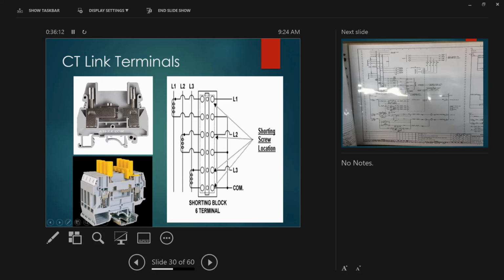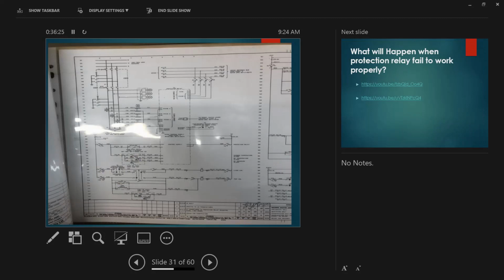That is the representation of the single line. This is from the CT, and this side will go to the relay. Mostly you can see this on the drawing like this. This is your protection relay, and this is your voltage. Of course, you have the feed from the VT going here, and the CT going here. If you test the relay, make sure that the VT is isolated. Because if that one is closed and the incomer is energized, you still have VT voltage here, and if you connect your test equipment over there, it will bugger the test equipment. Another 30 grand, according to Steve. So we have to be careful, especially when looking at the schematic, make sure that we're looking at the right schematic. On the VT, you have to open that, and on the CT, make sure that you inject on the right specific CT link.